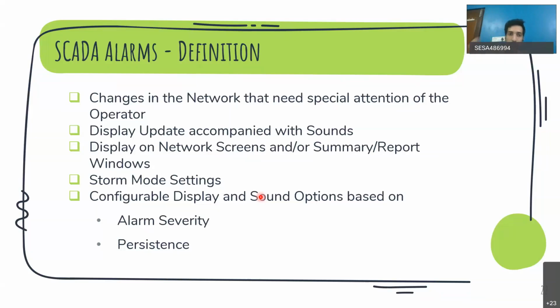So you can see on the display some blinking, plus sound also coming up to denote that something is wrong with this particular device or this particular substation or this particular location. Okay. And again, these displays and sound options are configurable. So for example, your substation breaker tripping at 66 kV or 33 kV may be of more importance than, for example, your LT breaker tripping. Okay, so for that substation breaker tripping you can configure a very irritating sound, so that the operator immediately turns his attention. Similarly, for an LT circuit breaker tripping, you may not even have configured a sound. So that way, it is very configurable.